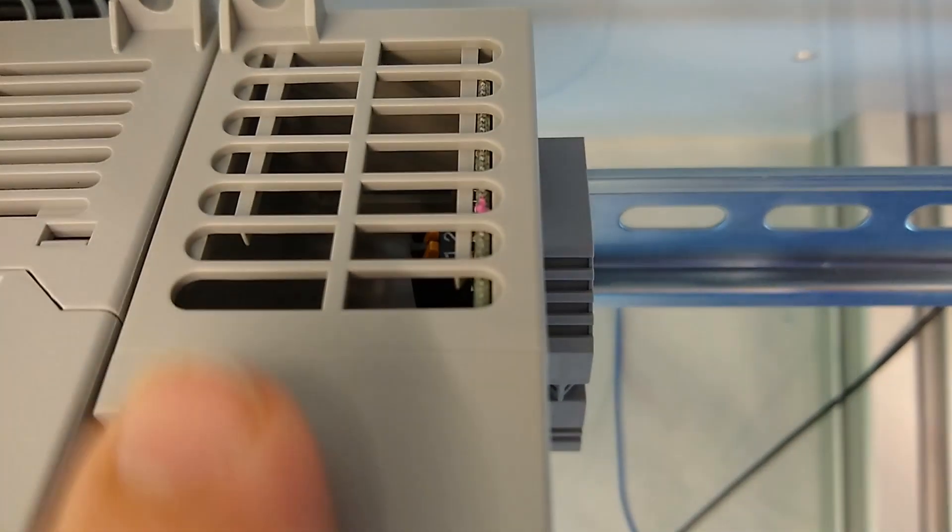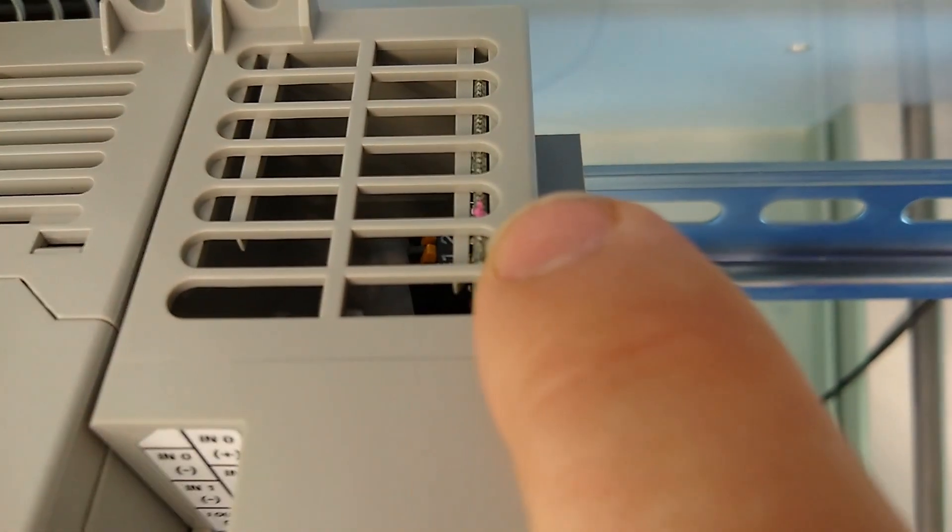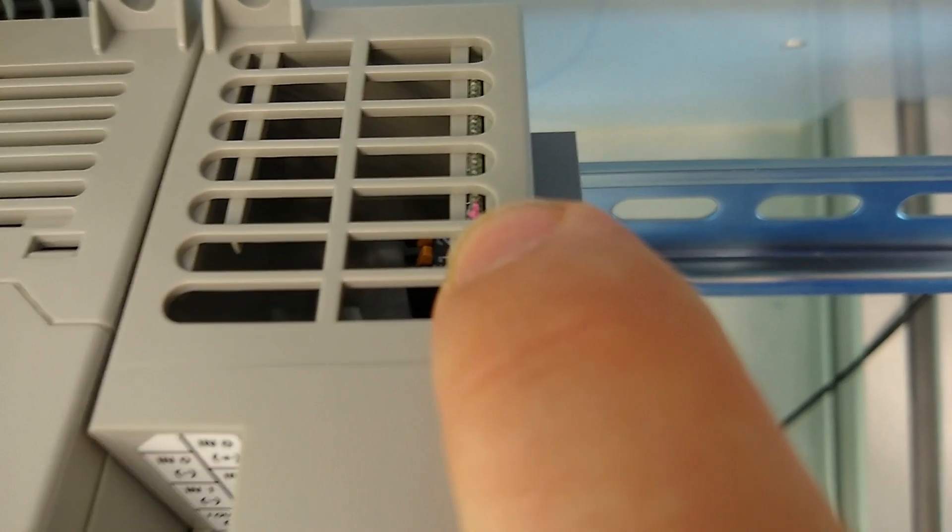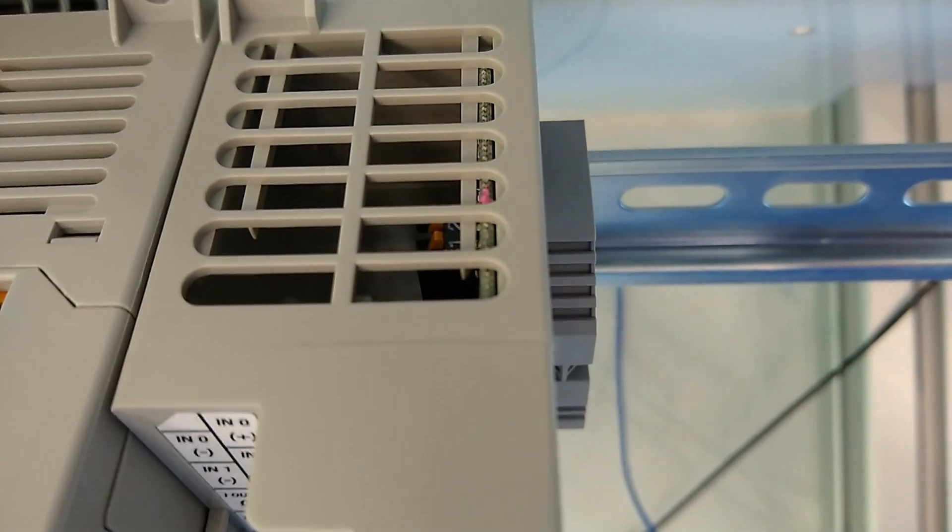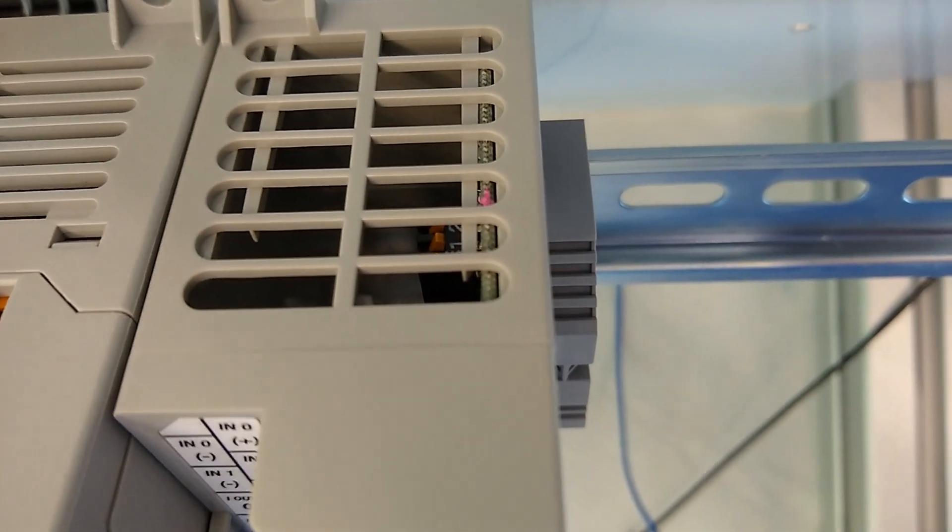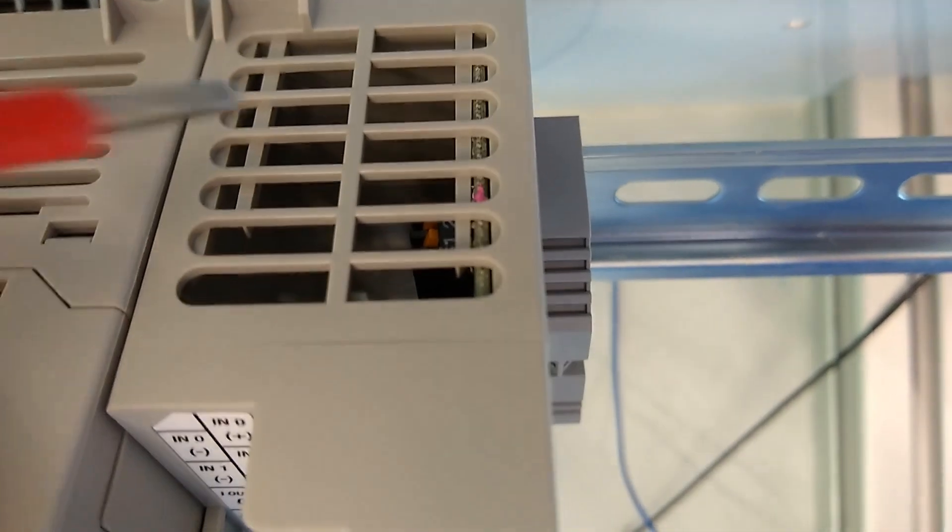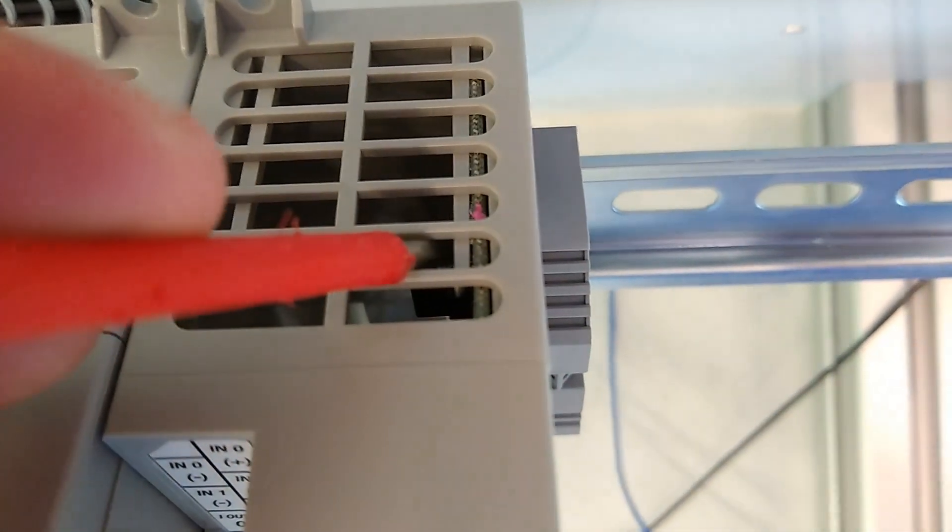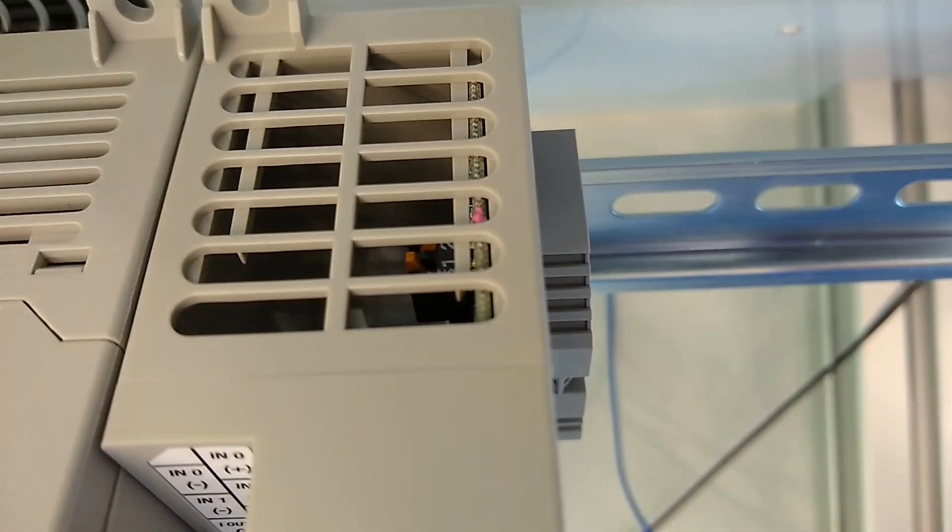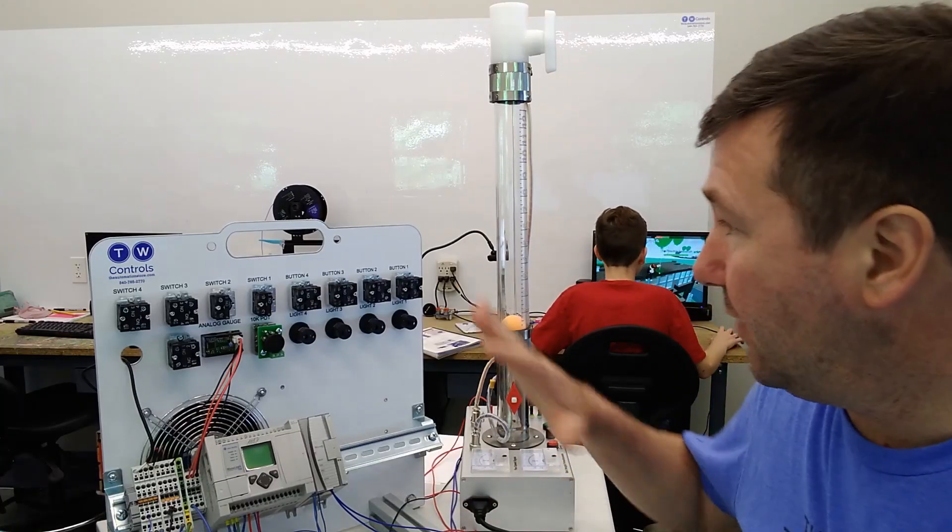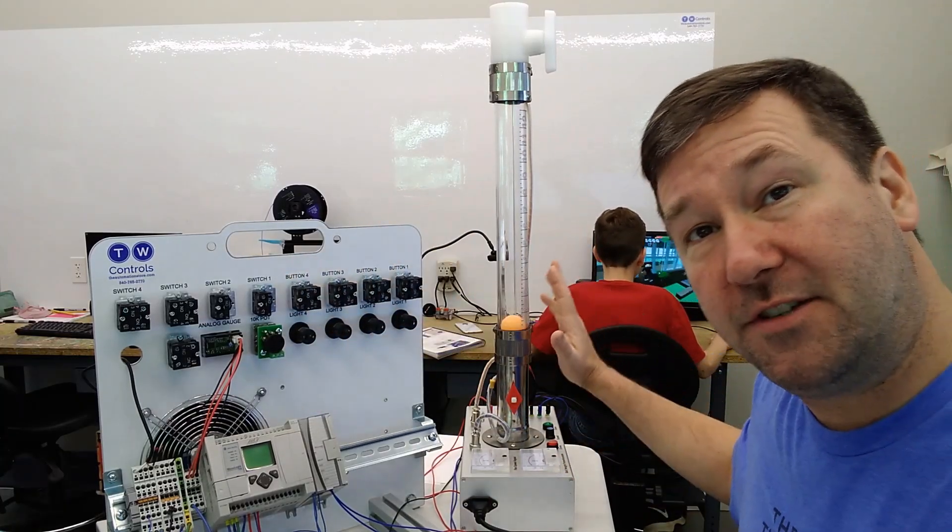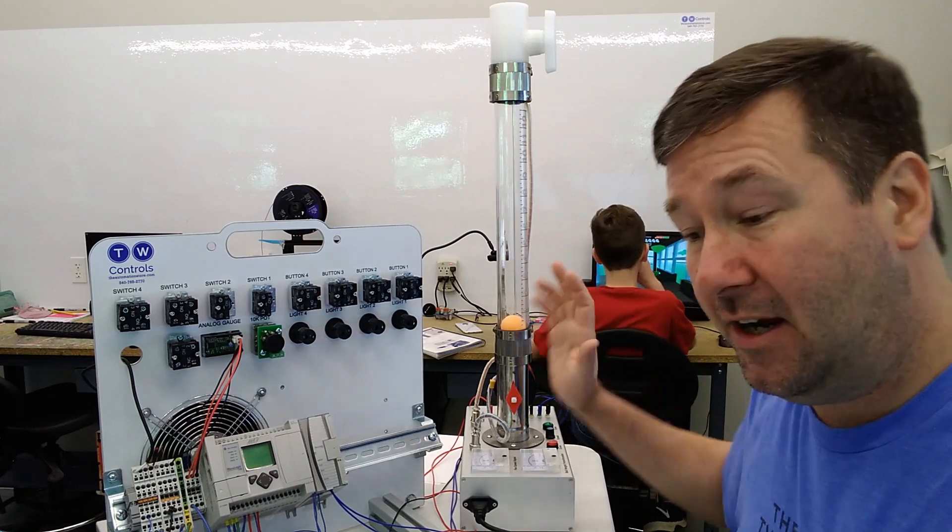One other thing is in the top of your 1762 IF2 OF2, there are two jumpers for the inputs, and these are your load resistors for milliamp signals. We're going to be using voltage signals, so we need to switch off. So there's the basics of our wiring to interface our PLC trainer with Industrial Concepts PID trainer.